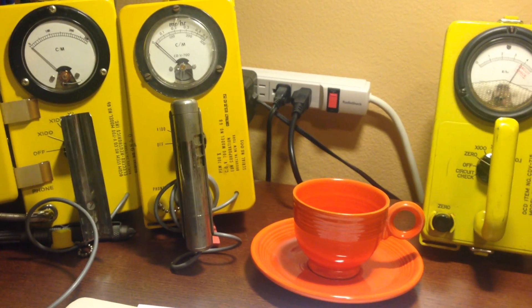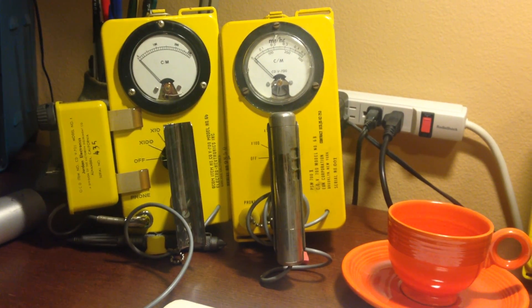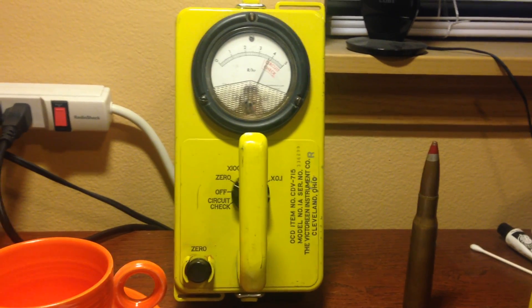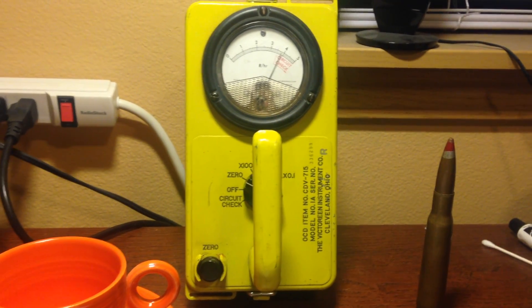A rate meter measures units of radiation per amount of time. The CDV700 model 6A on the left and 6B on the right measure beta radiation in terms of counts per minute, and measure gamma radiation in terms of milliroentgens per hour. The CDV715 measures radiation in terms of roentgens per hour.